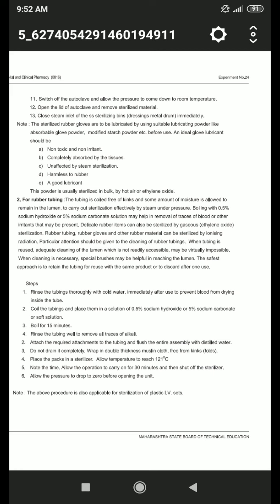Particular attention should be given to the cleaning of rubber tubings. When tubing is repeatedly used, adequate cleaning of the lumen, which is not readily accessible, may be virtually impossible. When cleaning is necessary, special brushes may be helpful in reaching the lumen. The safest approach is to retain the tubing for reuse with the same product or to discard it after one use. Now the steps: first, rinse the tubing thoroughly with cold water immediately after use to prevent the blood from drying inside the tube. Second, coil the tubing and place it in the solution of 0.5% sodium hydroxide or 5% sodium carbonate soft solution. Then boil for 15 minutes.